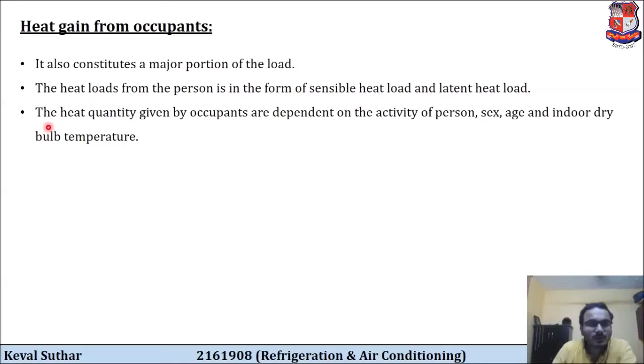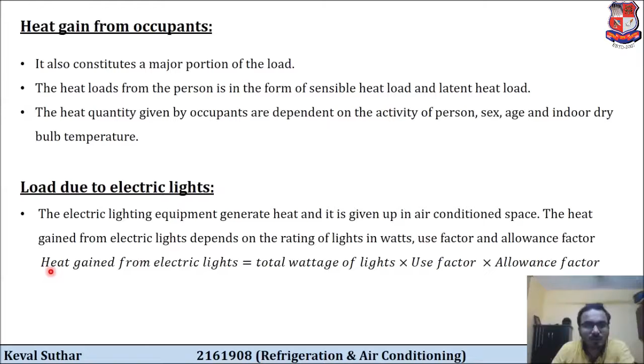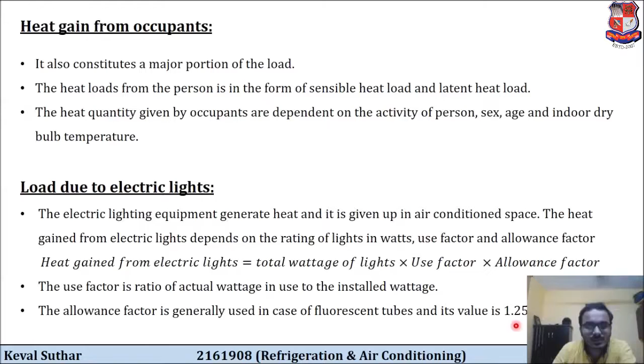Now the load due to the electric lights. The electric lighting equipment generates heat and it is given up in the air conditioned space. The heat gained from the electric lights depends on the rating of lights in watts, use factor and allowance factor. So this is the formula for that. That is, heat gained from the electrical lights is equal to total wattage of lights multiplied by use factor multiplied by allowance factor. Here the use factor, the second term, is the ratio of actual wattage in use to installed wattage. And the third factor, the allowance factor, is generally used in case of fluorescent tubes and its value is generally taken as 1.25. So this was the load due to the electrical lights.